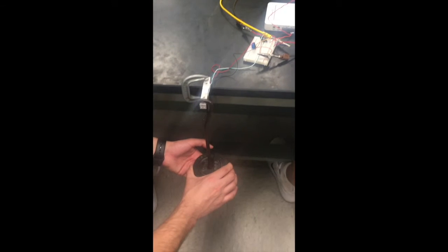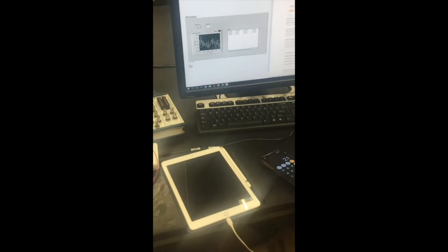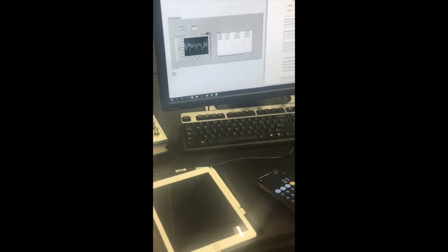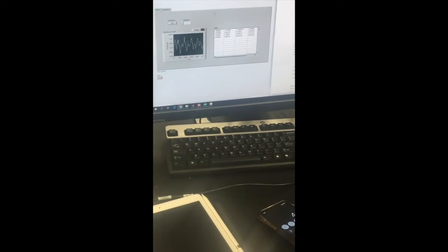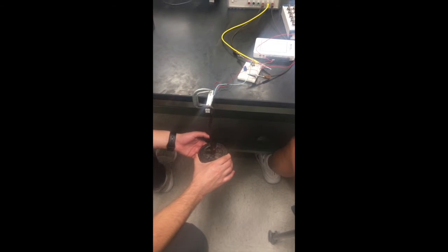Once the setup was completed, the team moved forward to perform the static calibration of the full bridge load cell. This was done by clamping the load cell onto a table and making sure it was oriented correctly. After this, the team recorded voltage and load data for an increasing and decreasing amount of load. This process was carried out for 8 iterations.